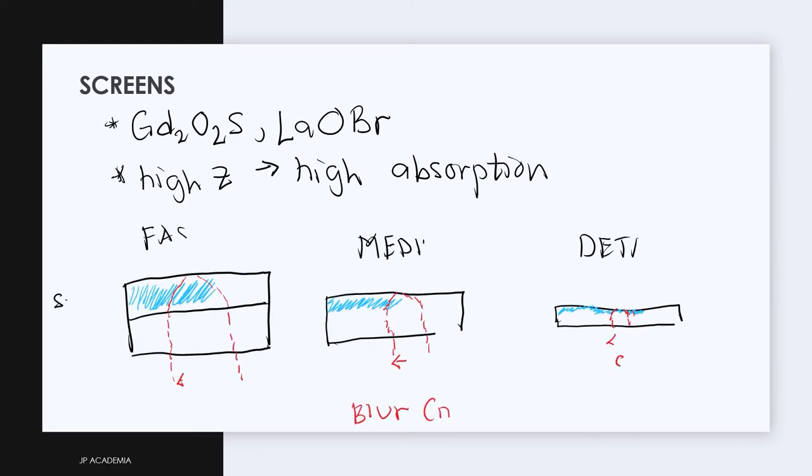The thickness of the screen affects the image blur. Thick screens absorb a large fraction of photons but produce large spread of photons that degrades the spatial resolution shown in this length a here.